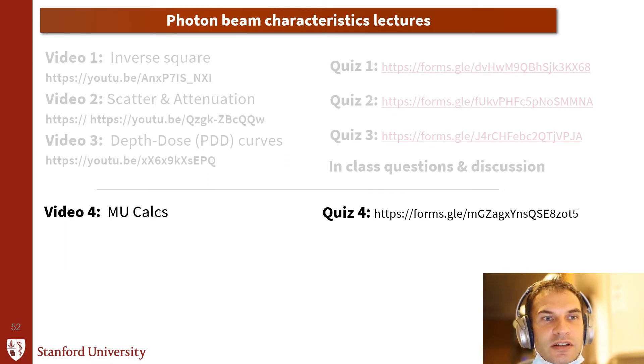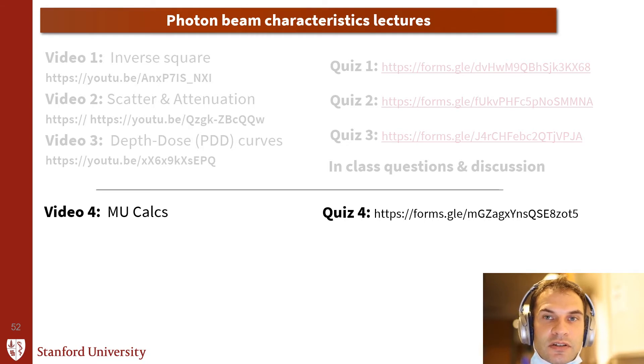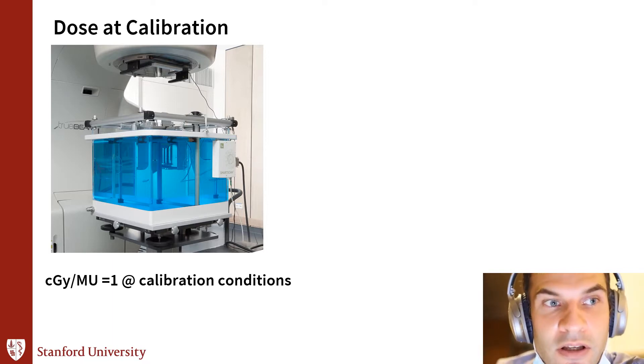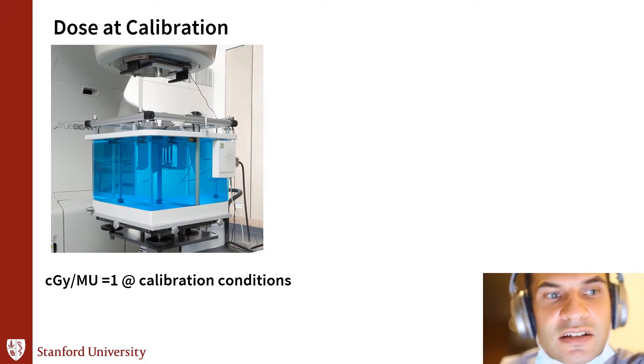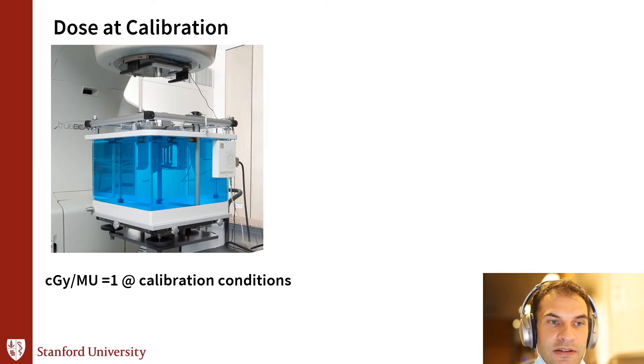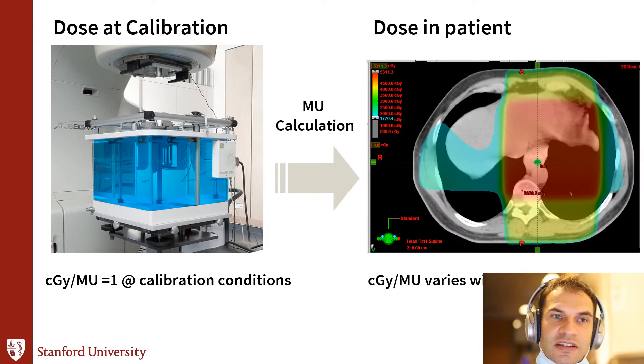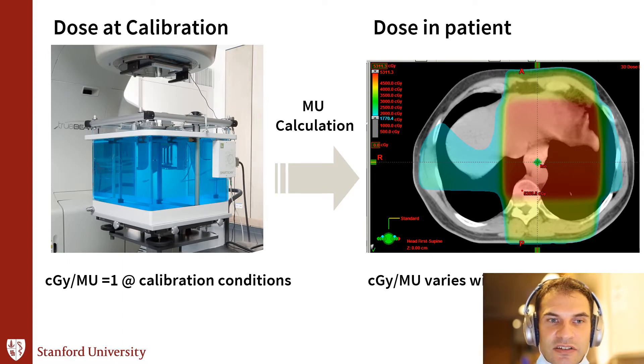So we've been through inverse square law, scatter attenuation, and depth dose curves. Physicists do dose calibration conditions in a water tank, and we ensure that the dose per monitor unit at these calibration conditions equals 1. But the difficulty is that a patient is not made of water, always at SSD 100, and always a 10 by 10 field size. So the dose per MU in the patient in the target volume varies — that's where the MU calculations come in.